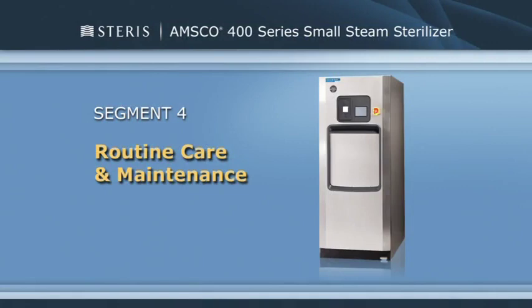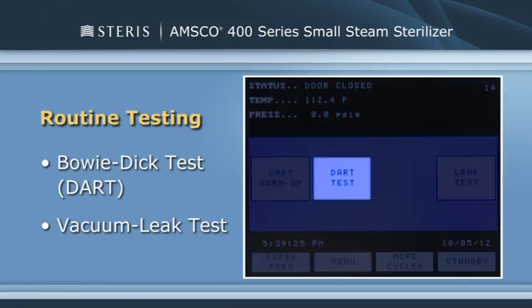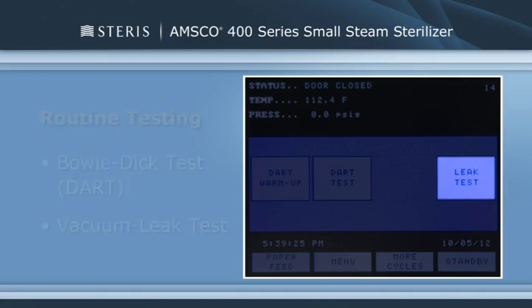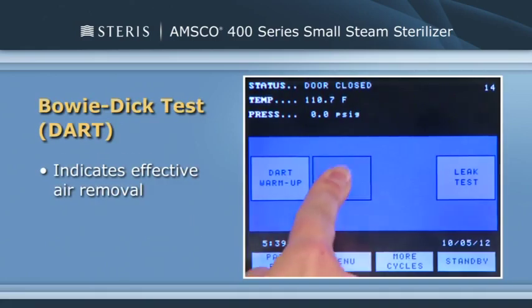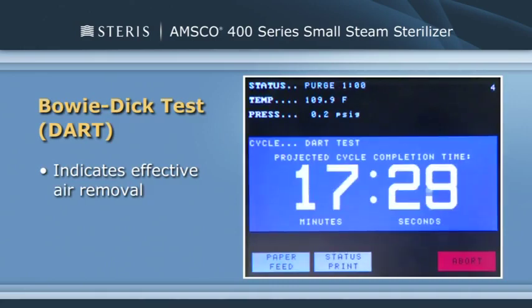Proper maintenance ensures a long and productive life for the AMSCO 400 series sterilizer. In this section, we'll cover the preventative maintenance schedule and procedures for the operator. For sterilizer monitoring, you'll run a Bowie-Dick or Dart test and a vacuum leak test. The Bowie-Dick test indicates if air has been effectively removed from the chamber and challenge pack.